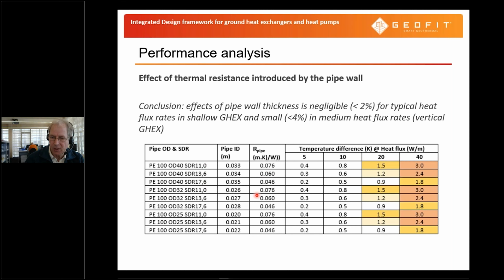But this seems to be just a value, so what does it mean? The thermal resistance of the pipe wall means that it introduces a temperature difference between the fluid and the outer pipe wall that also depends on the heat flux, on the capacity that we are using the ground heat exchanger for. And that is the heat flux in watts per meter. So if we have a low heat flux, 5 watts per meter, or a very high heat flux, 40 watts per meter, the temperature difference, of course, as a function of the thermal resistance and the heat flux changes.